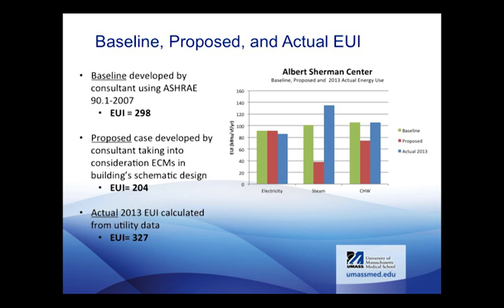So we identified 4 major ECMs for this process: first, reducing the enthalpy wheel speed, then optimizing the enthalpy wheel modulation sequence, implementing discharge air temperature resets, and then ventilation. We didn't look at lab ventilation, but specifically at ventilation in the office spaces. We reduced ventilation in office spaces across the board during occupied hours, and reduced it to 0 CFM during unoccupied times.